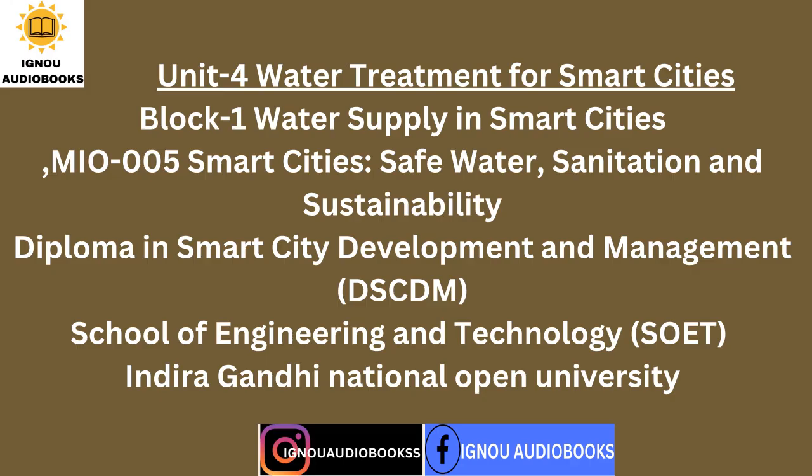Sedimentation. It is a unit operation in which inorganic suspended solids present in water are removed by the action of gravity. These tanks are designed to reduce the velocity of flowing water to give sufficient time for suspended particles to settle at the bottom of the tank. The efficiency of the tanks depends on the detention time period of the fluid mass after entering the tank and before exit from the tank (Davis, 2002). These tanks are rectangular or circular in shape.